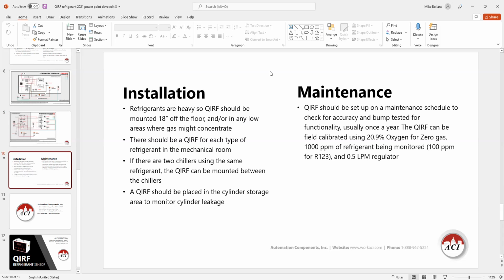Oh, the other thing, being that it's infrared technology, there are no sample tubes with our system because the sensors are so sensitive. I have a company here in Indiana, it's about 80 of these, and they did some testing. They were up to 75 feet away, dropping some Freon just to do some testing, and the sensors were picking it up almost simultaneously. That's how sensitive they are. So just to give you an idea on that too.